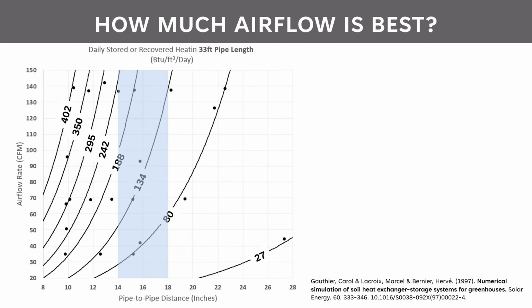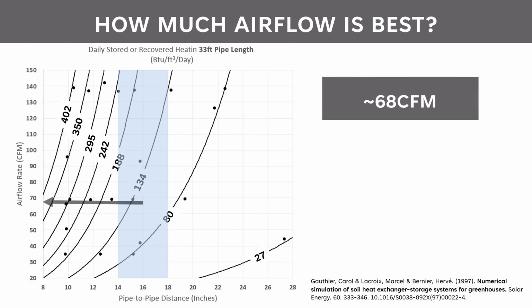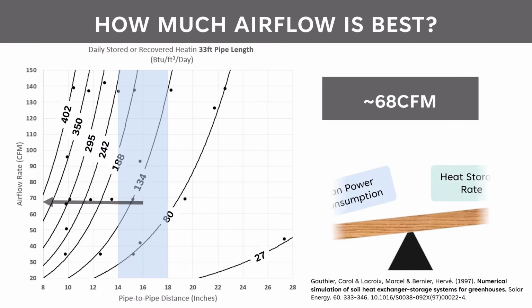To begin the discussion on how much airflow is best per tube, let's go back to this previous graph showing the pipe spacing, the airflow rate, and the heat storage per day. In the conclusions of the paper, they recommended about 68 CFM as the optimal airflow target. Why? 68 CFM is nearly optimal.